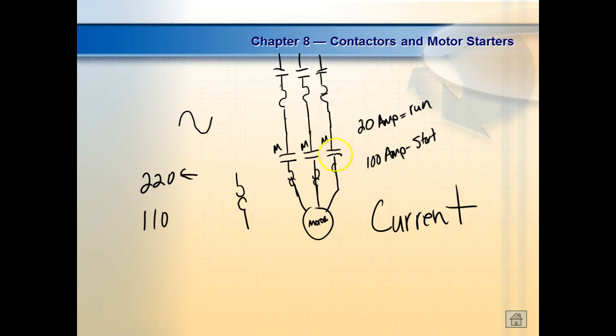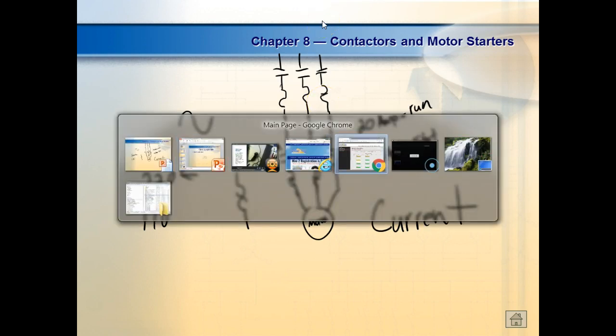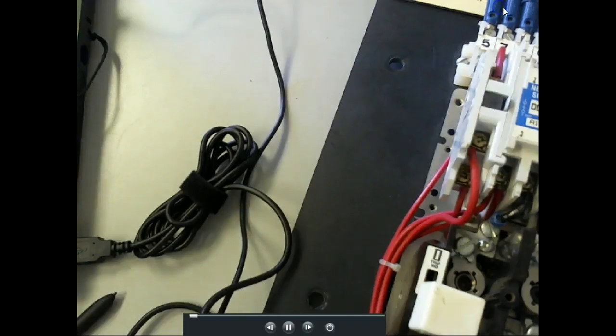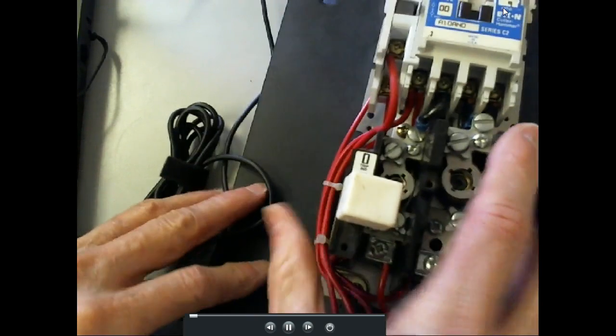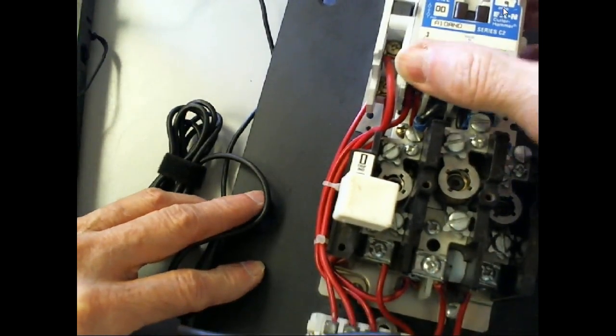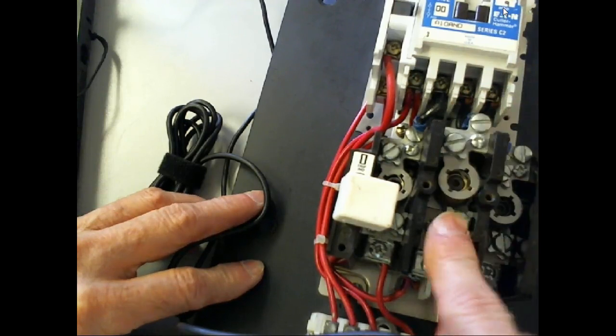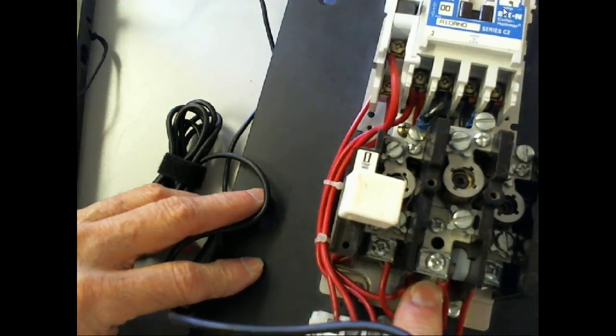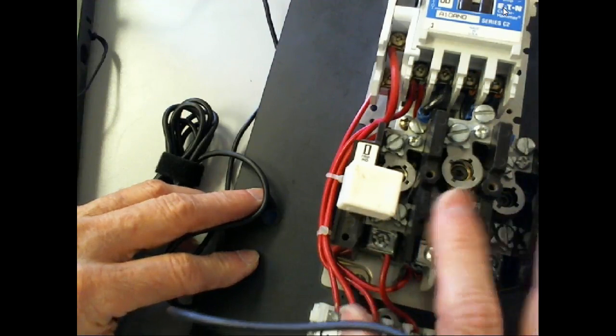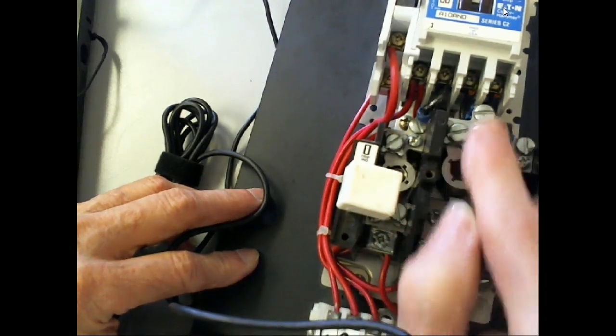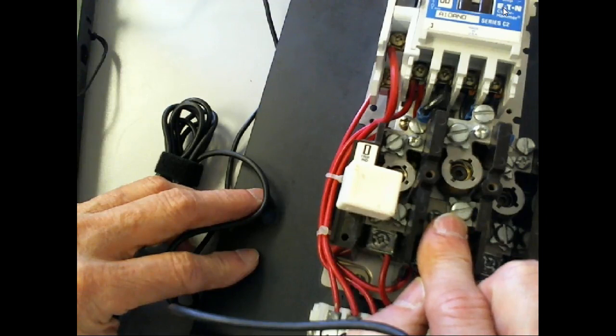So when, I'll do this backwards. They're overload sensors. So when I look at our magnetic starter, here's the output of the contactor. Then it connects directly to this. This is the overload sensor, and then the motor hooks down here. So all the current that's being pulled by the motor runs through the sensors, right? That makes sense.